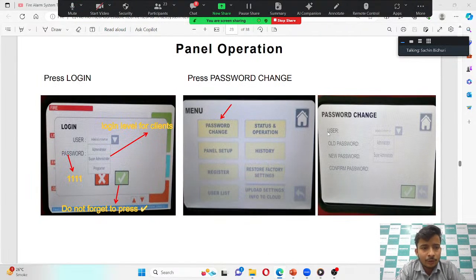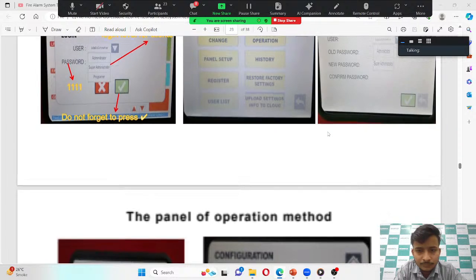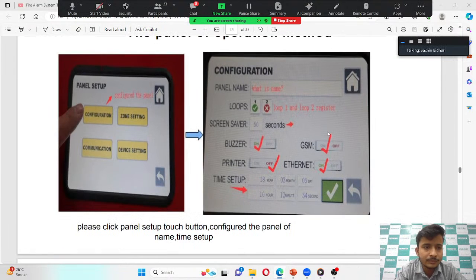From the panel, how can you operate? First of all, you need to log in to the panel. For login you select the type of user you are, like administrator, super administrator or programmer. Then you enter the password. The default password for this panel is 1111. You can also change the password from the panel as per your requirement.